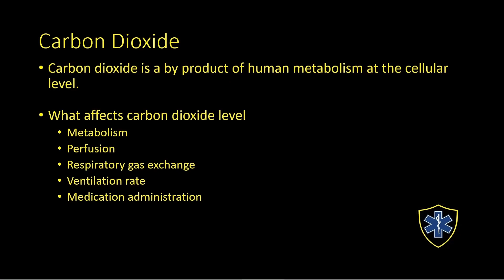We typically monitor what we call the end-tidal CO2, which is at the end of the patient's respiratory cycle, near the patient's mouth, or in the case of an intubated patient, at the tip of the ET tube. It's measured many times in millimeters of mercury, or a percentage of the exhaled volume. Now, we can monitor carbon dioxide with various different methods and different formats, and we'll talk about some of those. So one of the methods is qualitative. We can also have quantitative, and we can also even get a graphic representation of this.